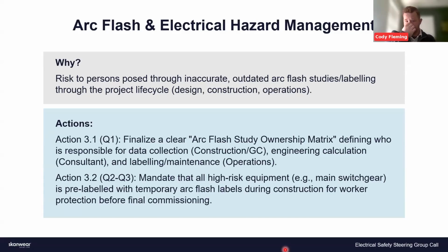A good tamper seal program is necessary to validate that your arc flash study is good in the future, because once it's turned over to operations—and I know my construction counterparts don't deal with this as much—you have a 5-year analysis required to revalidate your SCCS. Things change. Right now I'm helping with a couple of projects where customers are attempting to change breaker sizes, which will impact our SCCS. So then we have to go back through, revalidate everything, and do a full comparison.